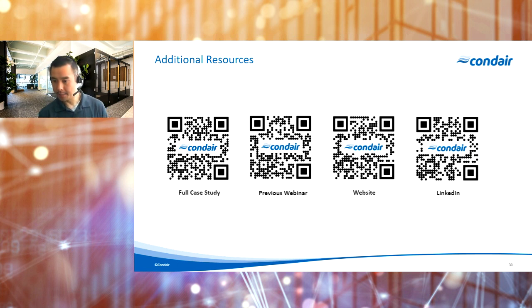Perfect. Thanks, John. There's a question here: can this be used in hospital HVAC systems for humidification with RO water per ASHRAE or CSA? So the quick answer there is, high pressure systems, yes. Evaporative systems, no. ASHRAE 170 a few years ago did open up and allow the use of high pressure atomizing systems within healthcare facilities for humidification. So atomizing systems are allowed. Evaporative media systems, as far as I'm aware, are still restricted.